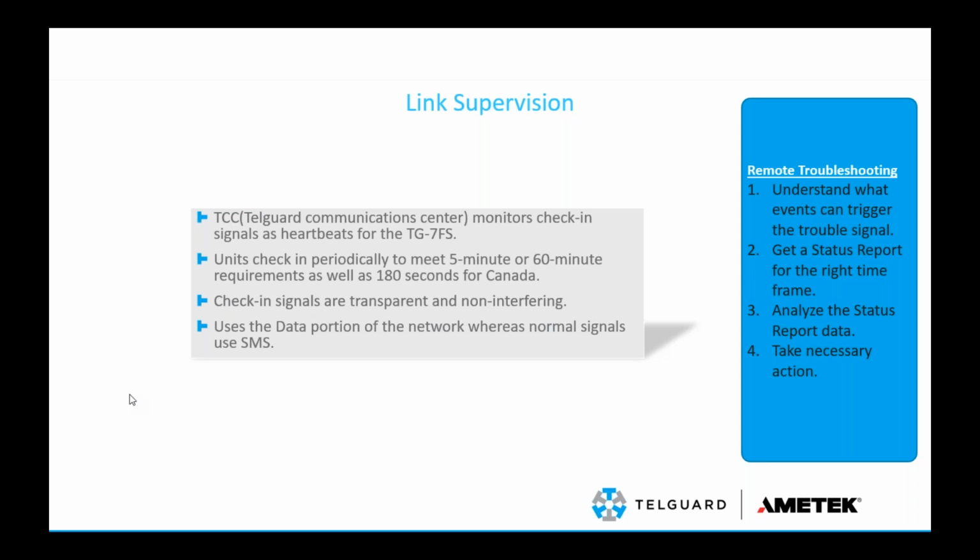I have a diagram in the next slide to break down a 60-minute supervision example, so you understand what those heartbeats are. We allow check-ins periodically to meet 5-minute or 60-minute requirements in the US, as well as 180 seconds for Canada if we have any Canadian dealers on the line.